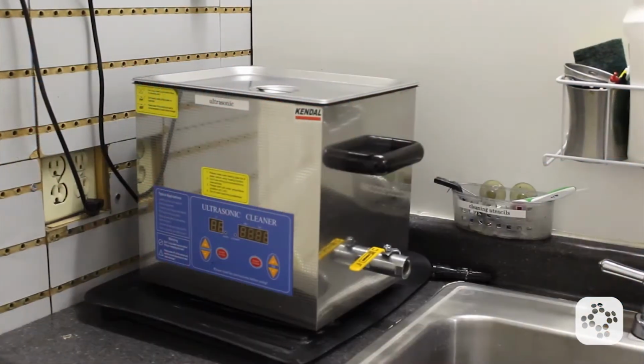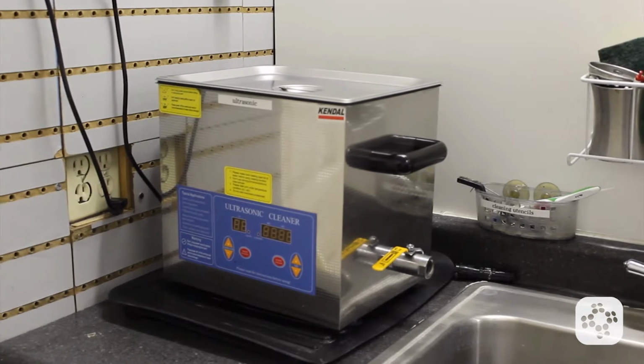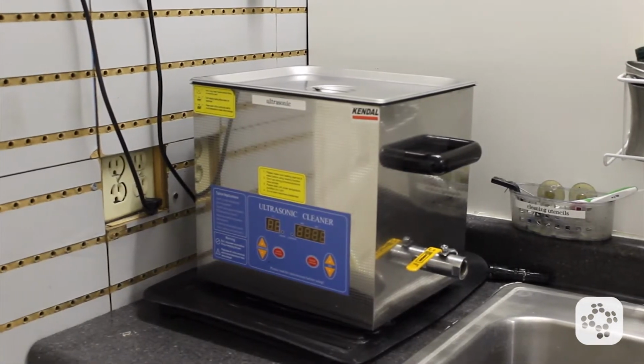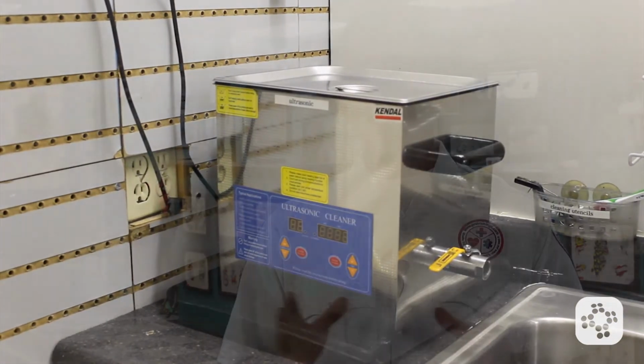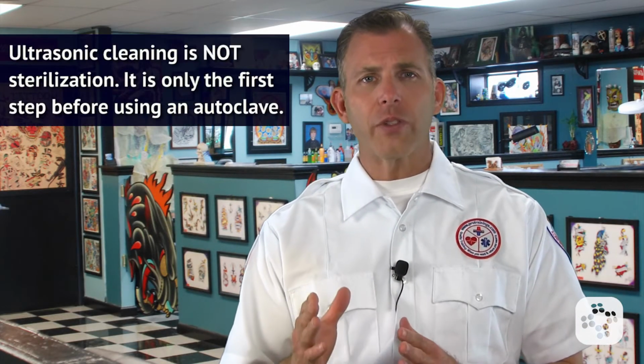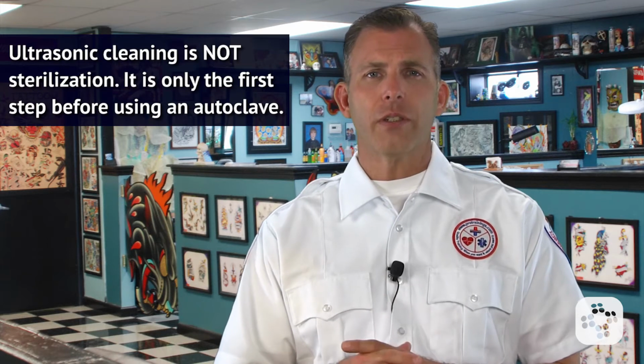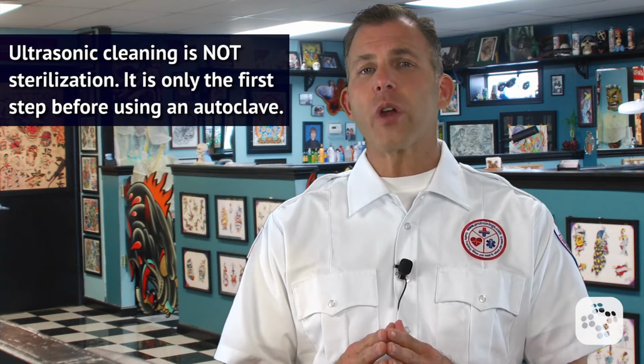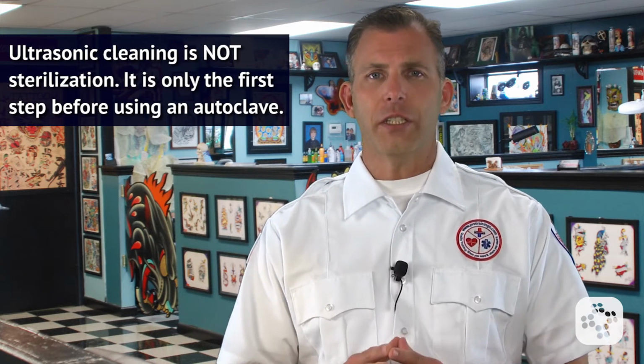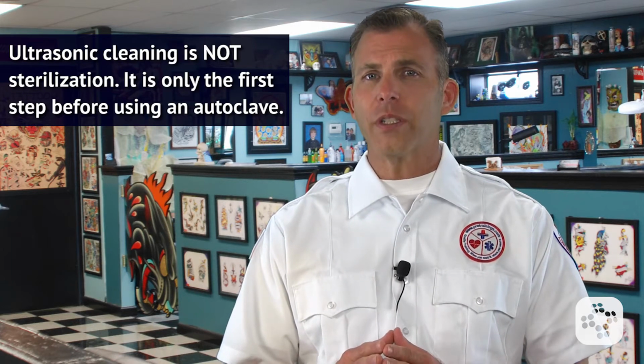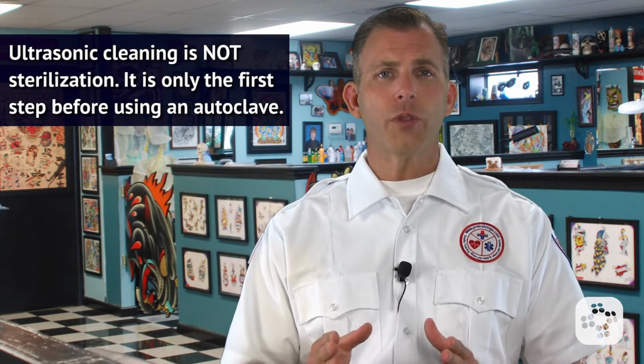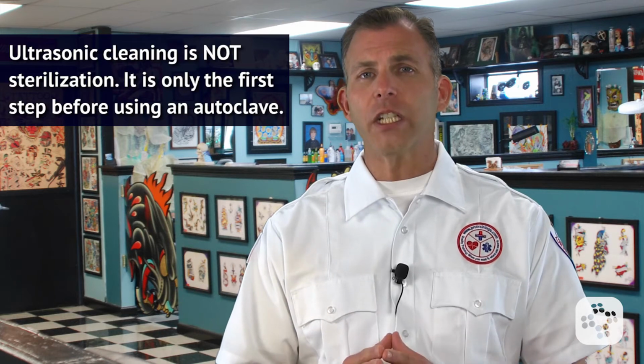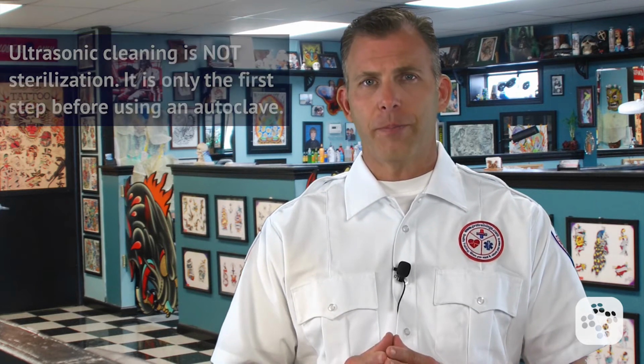Fourth, cleaning. In general, there are two approaches to basic disinfection: ultrasonic cleaning and hand cleaning. Don't mistake ultrasonic cleaning of instruments for sterilization. Ultrasonic cleaning uses ultrasonic waves and an appropriate cleaning solvent. Follow the manufacturer's instructions for use of the ultrasonic cleaner. It's also important to disassemble grips, tubes, and tips after ultrasonic cleaning to allow for further cleaning.